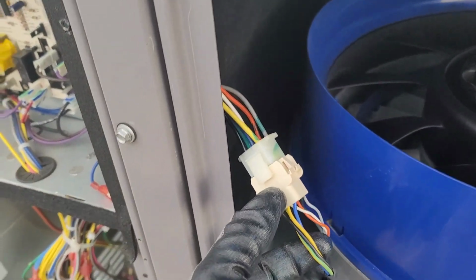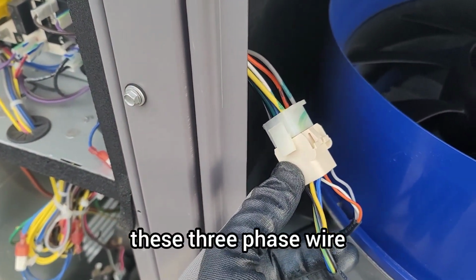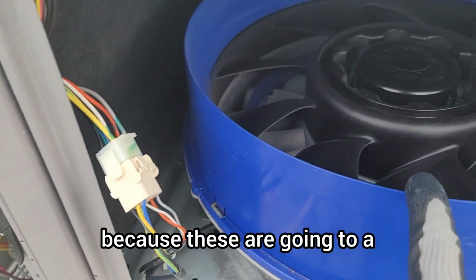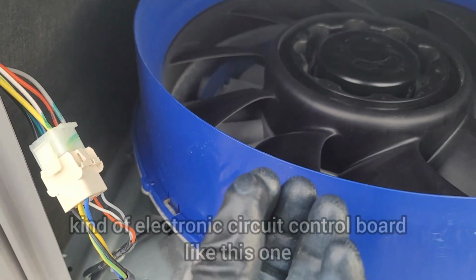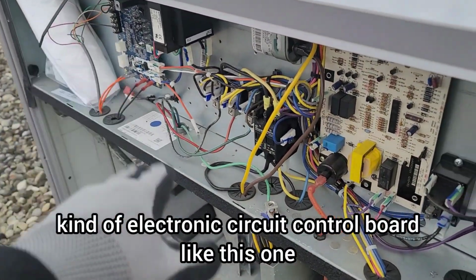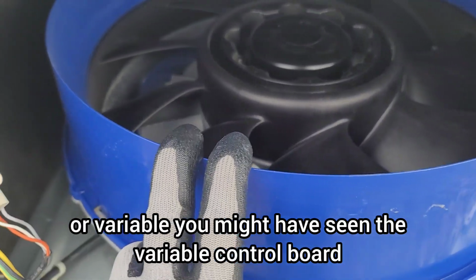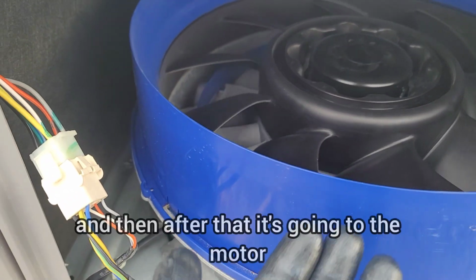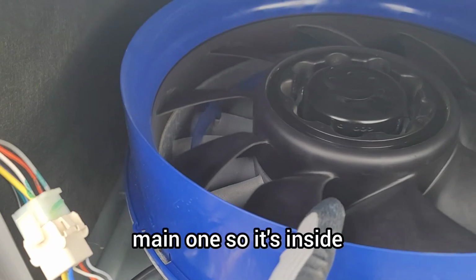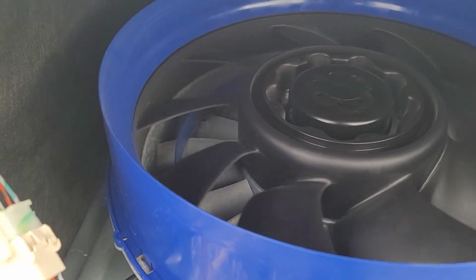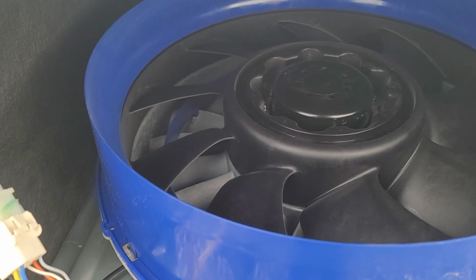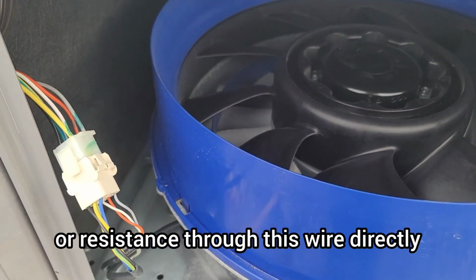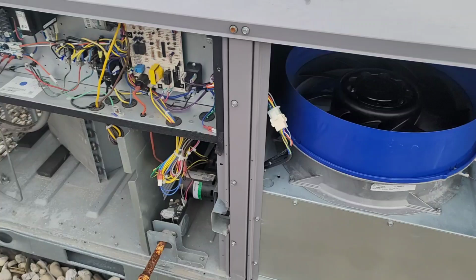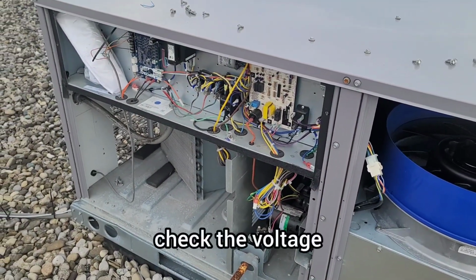So my point is, we cannot check the winding from these 3 phase wires, because these are going to, I think, the ECM module, which is an electronic circuit control board like this one. You might have seen the variable control board, and after that it's going to the main motor. So it's inside. So we cannot check the continuity or resistance through this wire directly. So let's turn on the power, check the voltage, low voltage and everything.